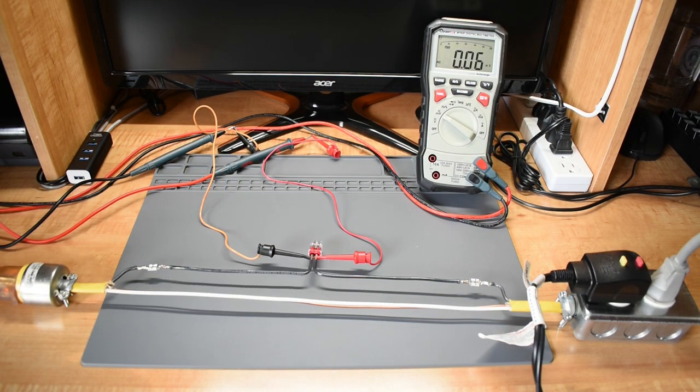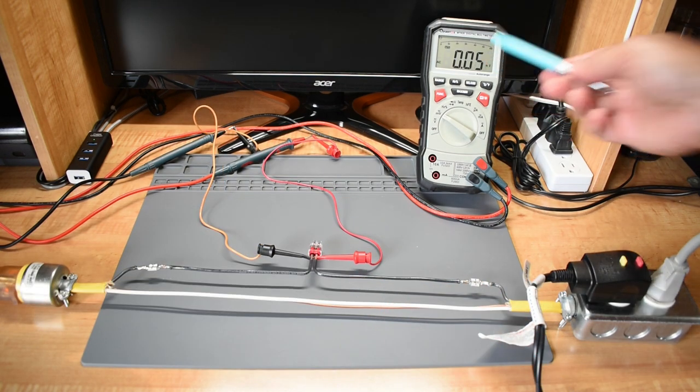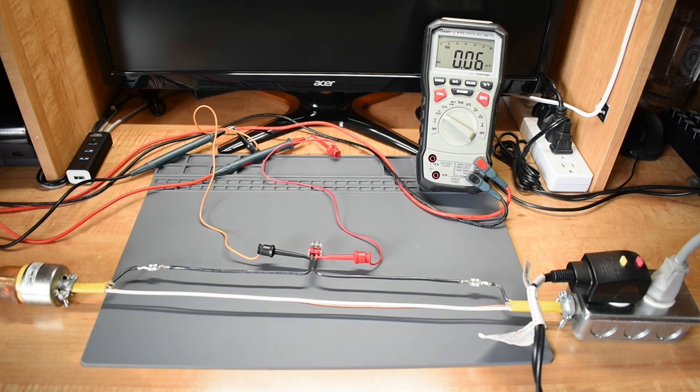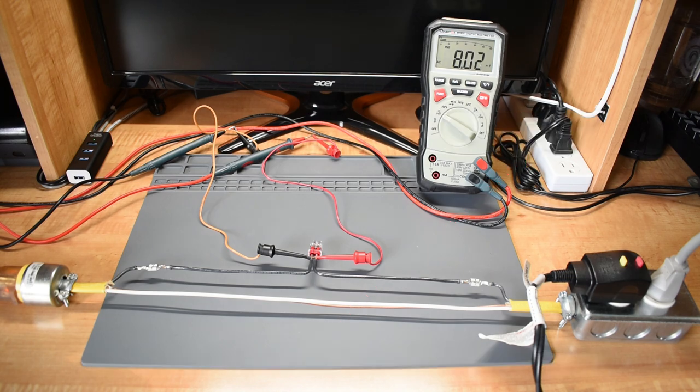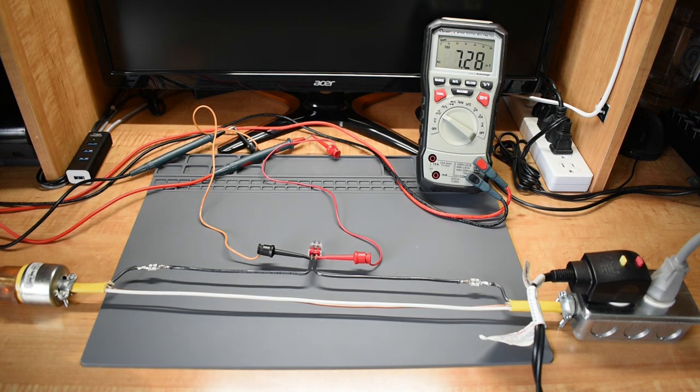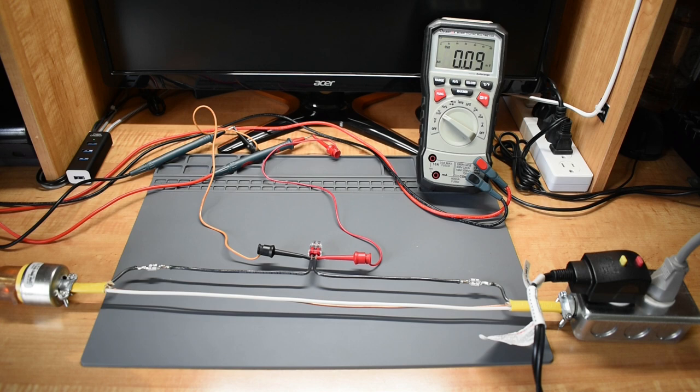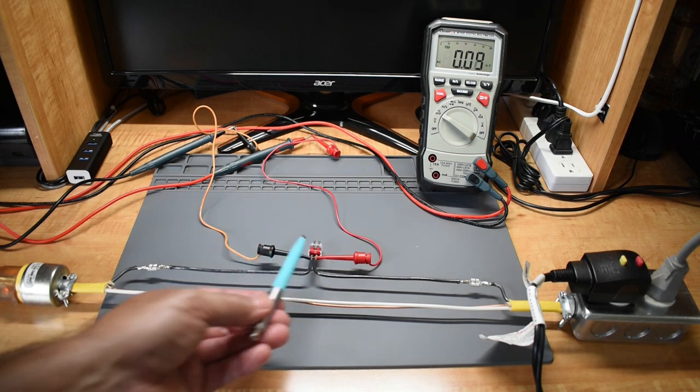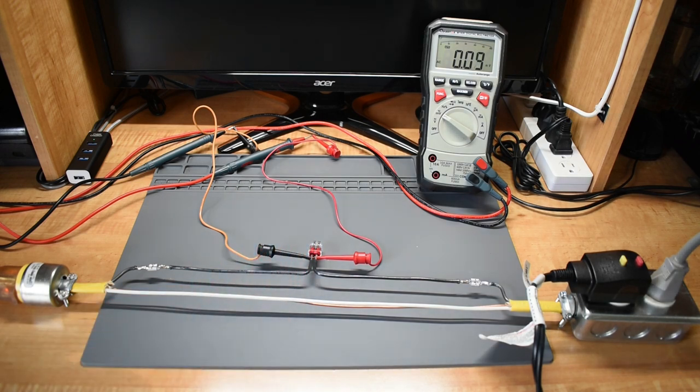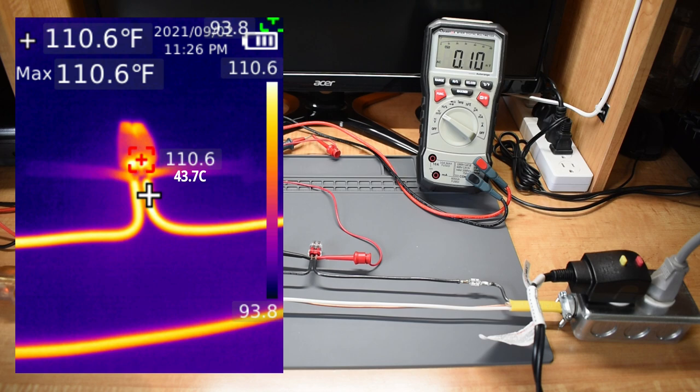We're now going to test the Ideal connector, same as before, deduct 0.05. The Ideal connector was right around 8.2 millivolts, so definitely higher, because less surface area of the wire is making contact. Right here you can see the temperature, and it's a little higher than the wire nut.